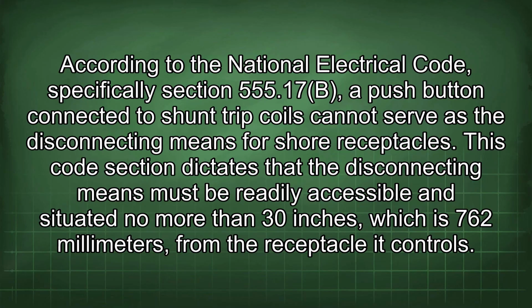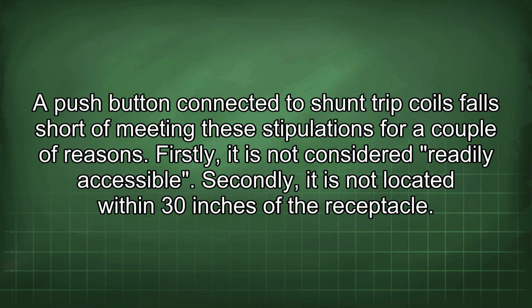According to the National Electrical Code, specifically Section 555.17(B), a push button connected to shunt trip coils cannot serve as the disconnecting means for shore receptacles. This code section dictates that the disconnecting means must be readily accessible and situated no more than 30 inches, which is 762 millimeters, from the receptacle it controls. A push button connected to shunt trip coils falls short of meeting these stipulations for a couple of reasons.